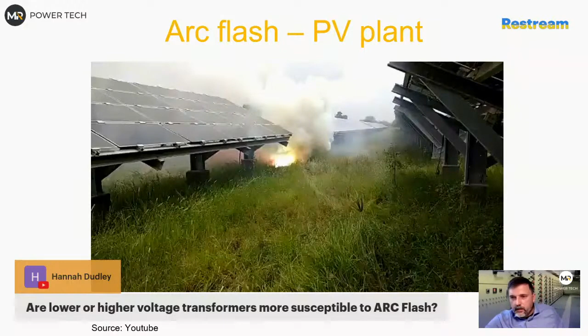I didn't mention that arc rating, the internal arc classification, is almost mandatory now, or almost included in 9 out of 10 switchgears or 99 out of 100 switchgears on medium voltage. They will be tested according to internal arc classification. From low voltage equipment, it's rather 1 out of 100 that has some kind of arc rating. And I think it's because it's bringing the cost up, and it's probably much more practical to install arc flash detection systems, arc flash relays, than make switchgear arc rated if people would just go there and open everything eventually.